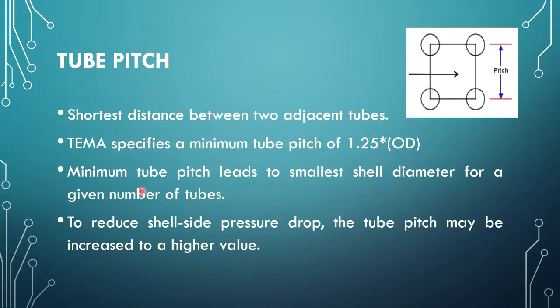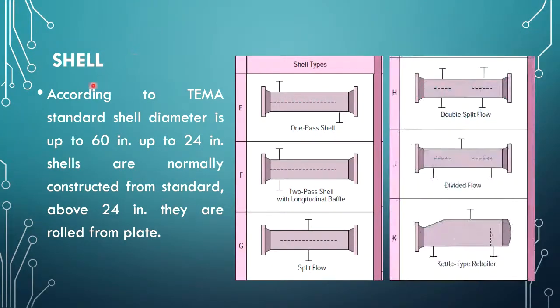Next is the shell. The shell is a main important part of the shell and tube heat exchanger — it covers the tube bundle inside. According to TEMA standards, shell diameter is up to 60 inches. Up to 24 inches, shells are normally constructed from standard pipe, and above 24 inches they are rolled from plates.